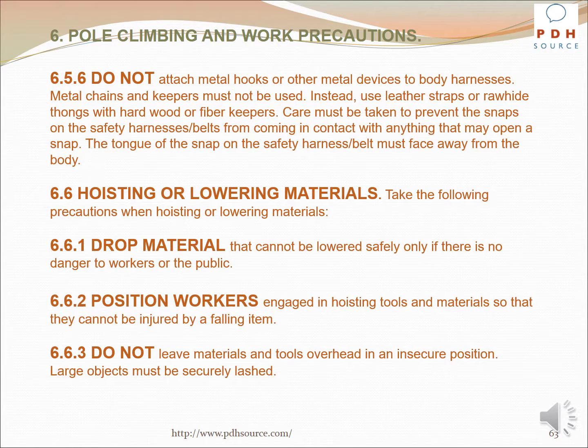Do not attach metal hooks or other metal devices to body harnesses. Metal chains and keepers must not be used. Instead, use leather straps or rawhide thongs with hardwood or fiber keepers. Care must be taken to prevent the snaps on the safety harness belts from coming in contact with anything that may open a snap. The tongue of the snap on the safety harness belt must face away from the body.